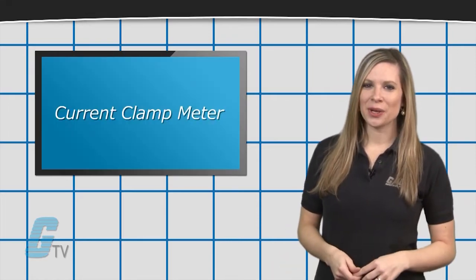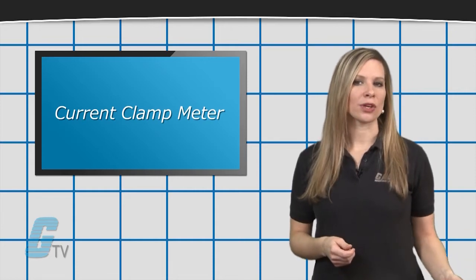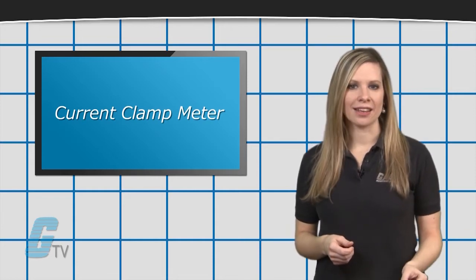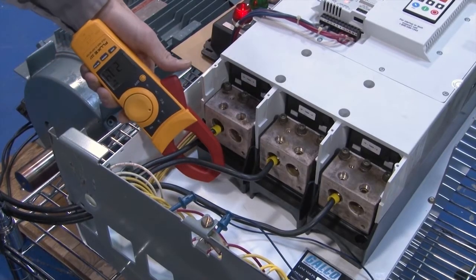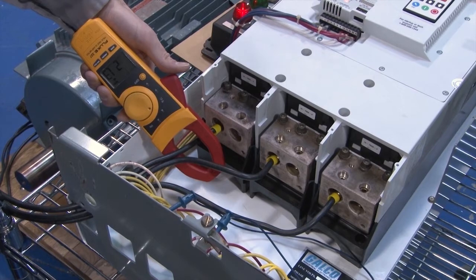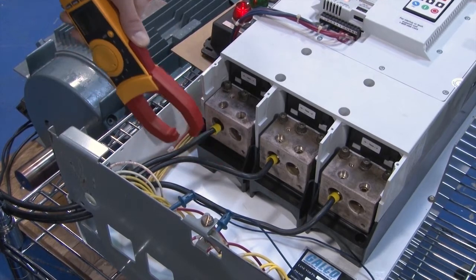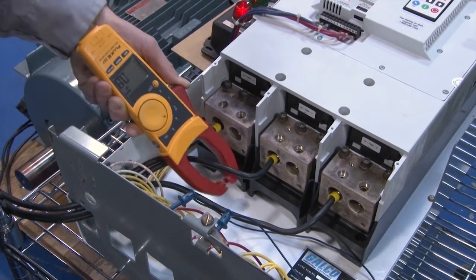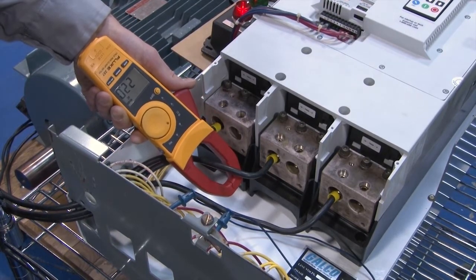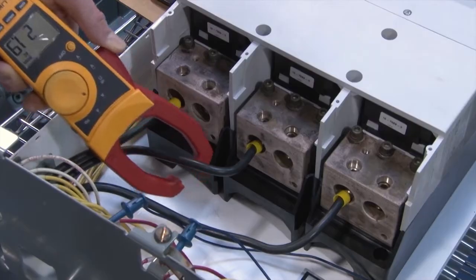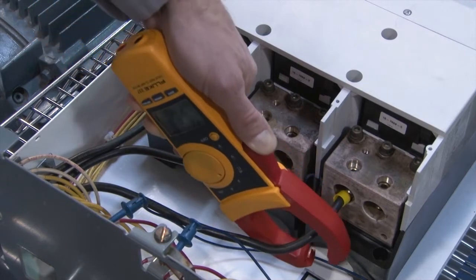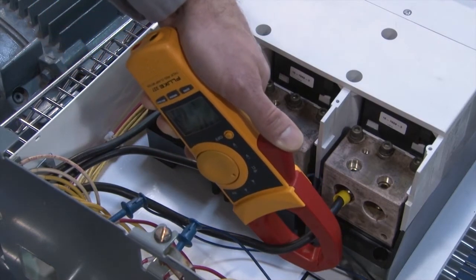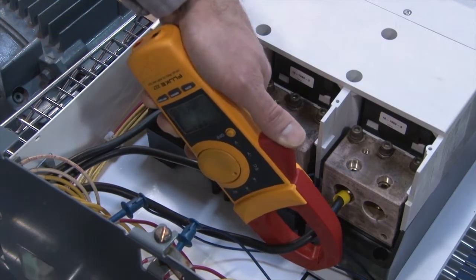For checking current, a current clamp meter is needed. This can go around each conductor on the output side of the drive to verify that a similar amount of current is being drawn and to see if there is any phase imbalance.